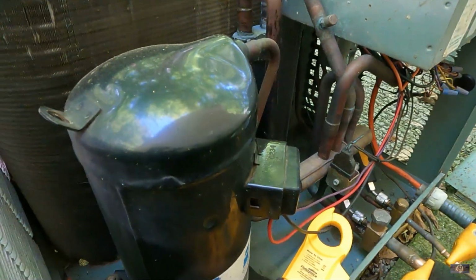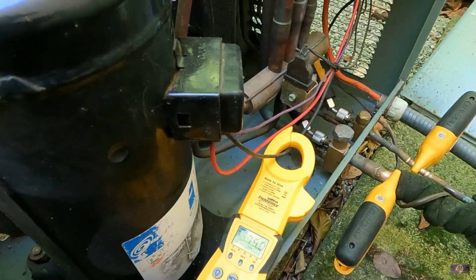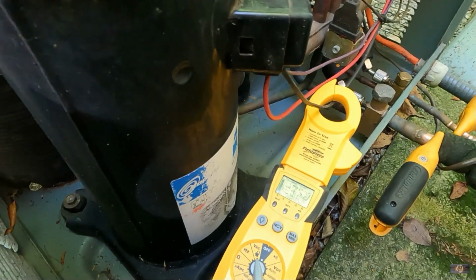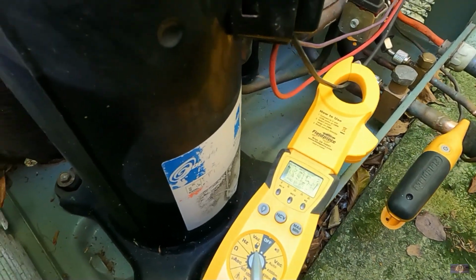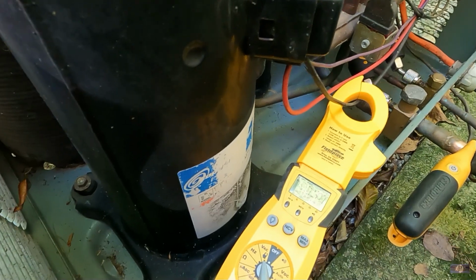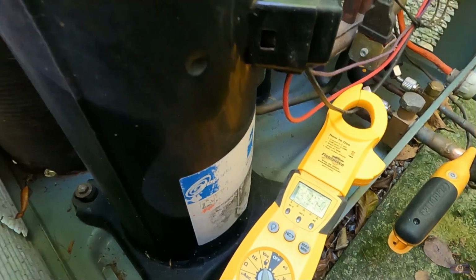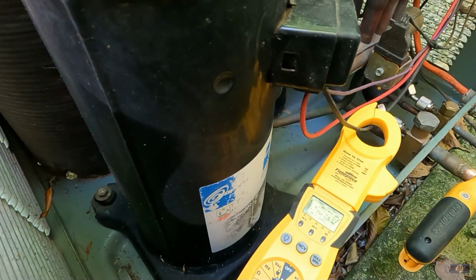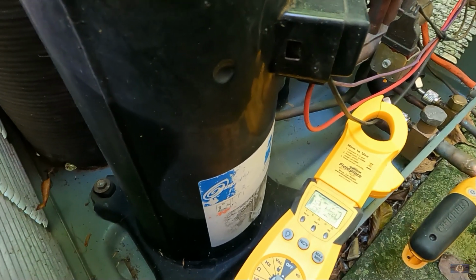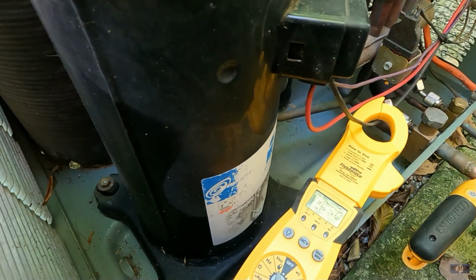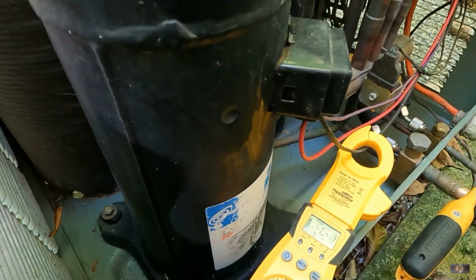These systems are oversized for the space. I did not install these. Whoever installed these, I know who did it, but I'm not going to mention any names. They were overcharged, vastly overcharged, and the ductwork is undersized for these units. But they are now at 19 years old and still kicking. I've tried to dial it in best I can.